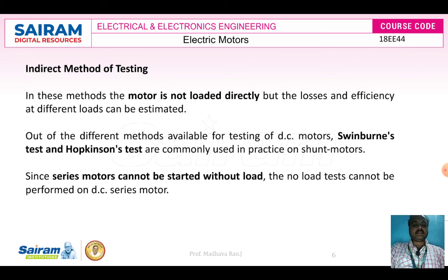So no load tests cannot be performed on a DC series motor. That is the main important thing. Series motors always start with load. If you start without load, it will run at a dangerous high speed, and automatically the armature and field winding will get damaged. Then the armature winding and field winding of the series motor need to be replaced. So this is about testing of DC motors.